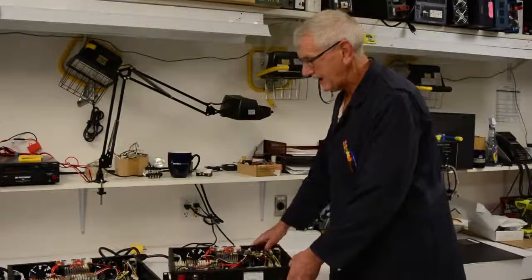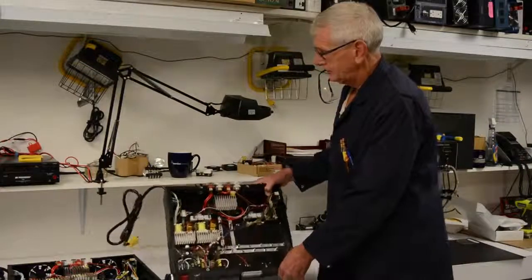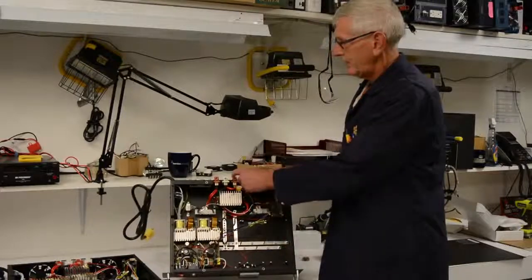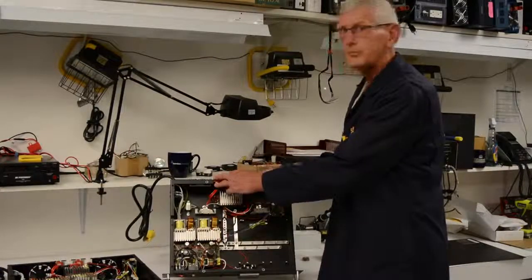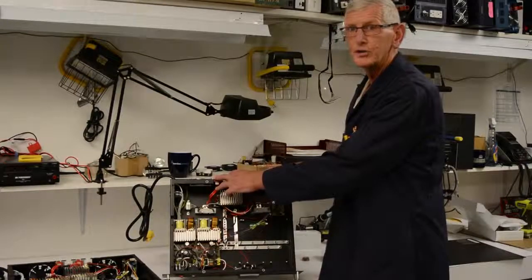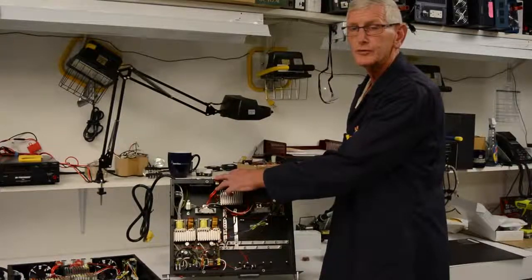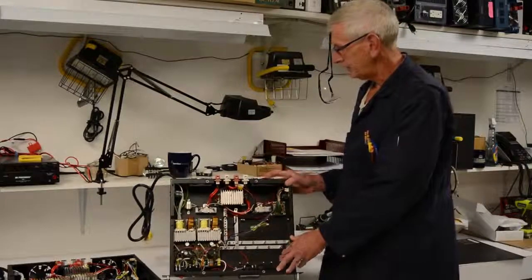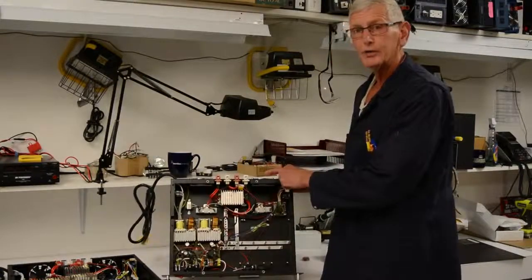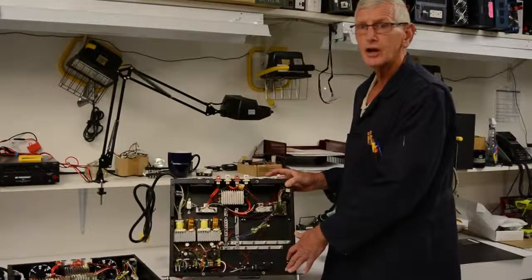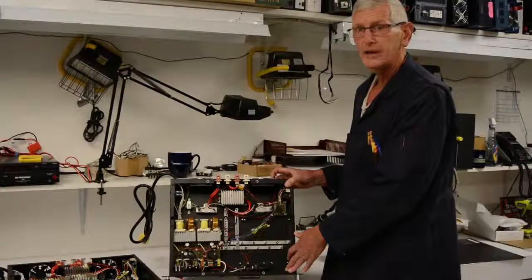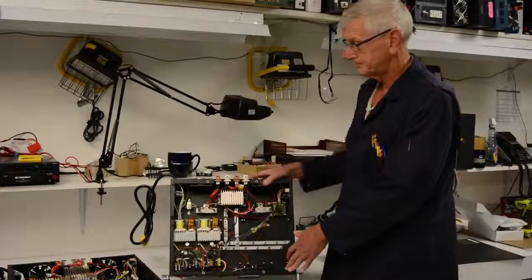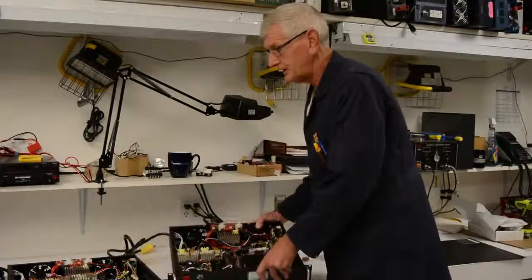On the back side, we have the load terminals for your DC load and the battery terminals. This is where you would have your battery bank attached for a battery backup. There's also an alarm output which has isolated alarms for any of the statuses of any of the modules and the status of the unit itself. So that's the main features on the unit.